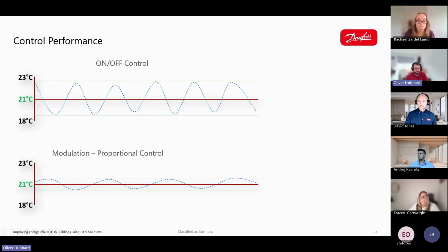So here we have two charts, one showing on-off room control and the other showing modulating. As you can see, the on-off is over and undershooting the set point by approximately 2 degrees each side, so it's going up and down, which overall isn't efficient and generally reduces comfort for whoever's occupying that particular room. Below we have a chart for modulating control, which reduces the fluctuations to approximately 0.5 degree either side of the set temperature, which is more efficient and has less impact on the comfort of whoever's in that room.